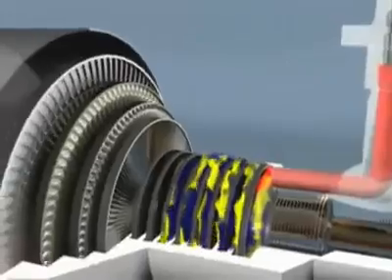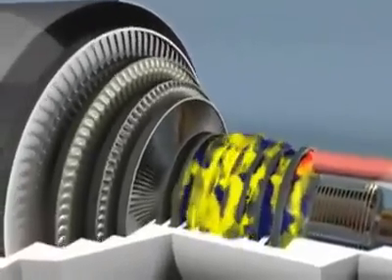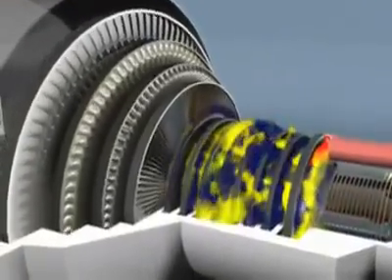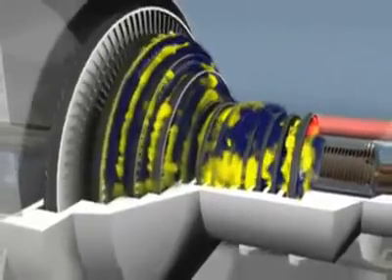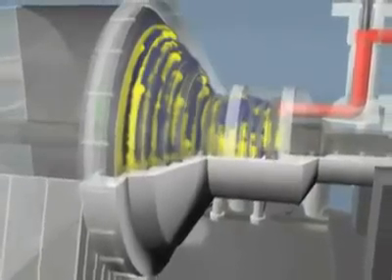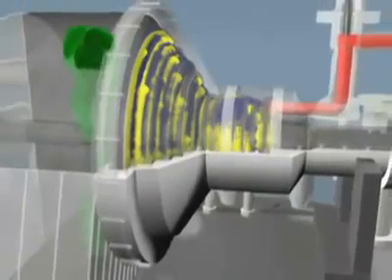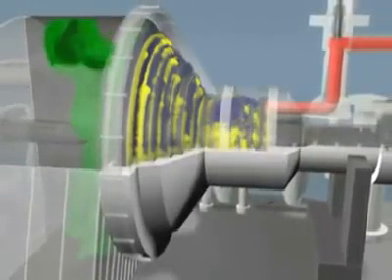As the steam flows through each stage of blading, it expands as it transfers its energy to the rotor. So each stage of blading is larger to capture as much energy as possible. After the steam passes through the turbine steam path, it's exhausted into a condenser, turned back into condensate and returned to the boiler to be made into steam once again.